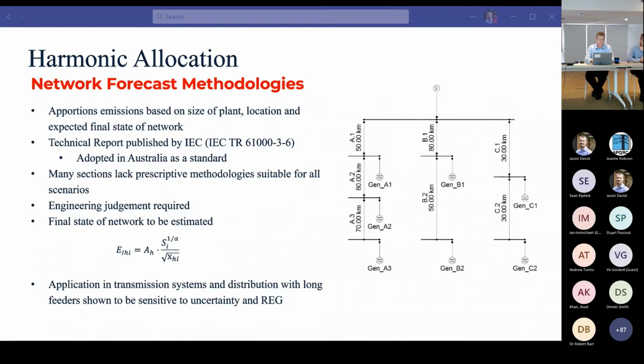Now, if this assumption is incorrect, it's very possible that the harmonic absorption capability of the network will not be adequately utilized. What we can show is that it may result in planning levels being exceeded by a margin. In some cases, that margin can be quite large, or the network can be significantly underutilized and your planning levels only fractionally utilized, resulting in an increased amount of harmonic mitigation that may be required, increasing costs to generators or distorting customers in general, and ultimately resulting in an inefficient management process.